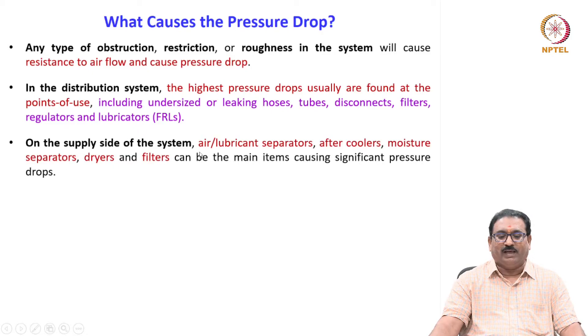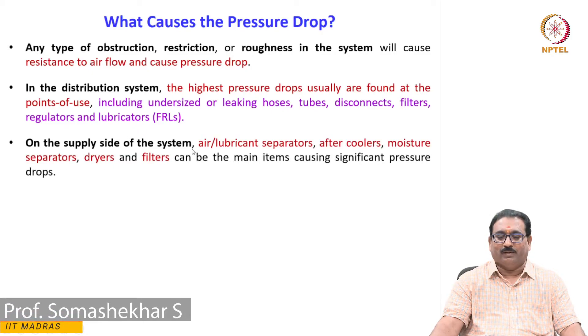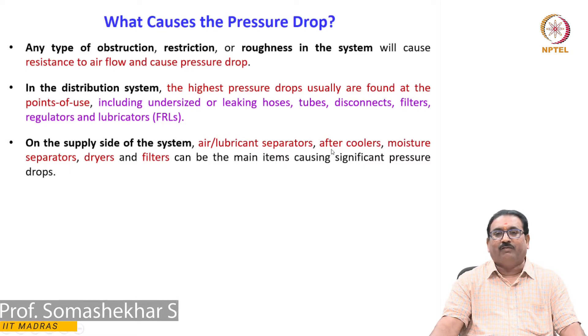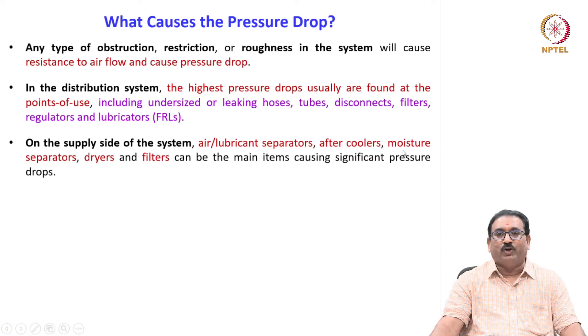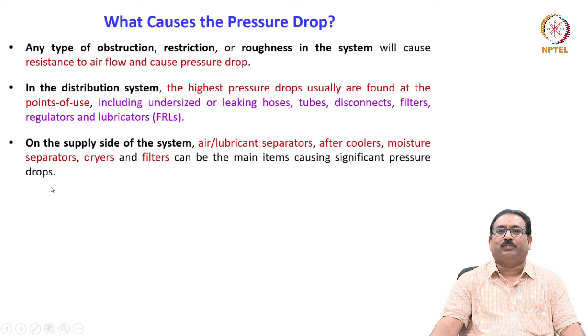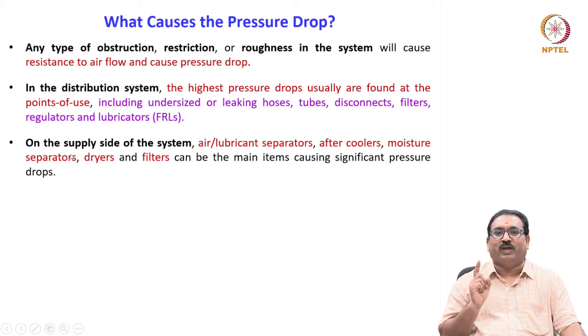On the supply side of the system, air-lubricant separators, after coolers, moisture separators, dryers, and filters can be the main items which cause significant pressure drop. Both at the point of use and at the generation side, you have to take much care in reducing the pressure drop.